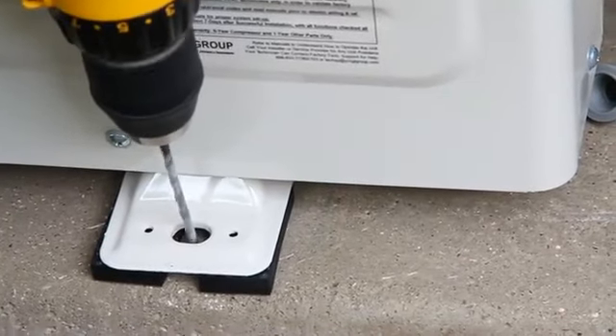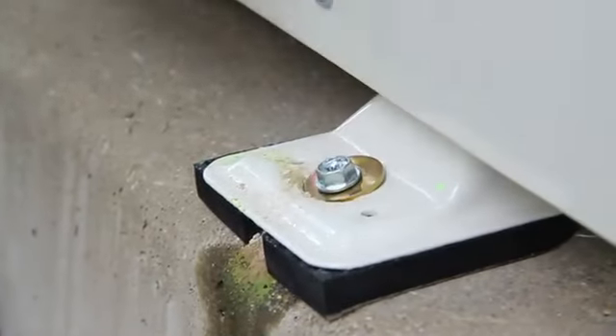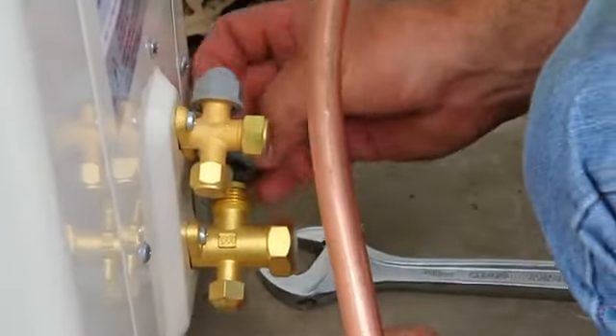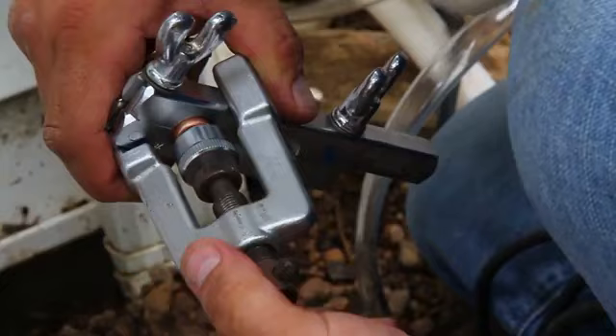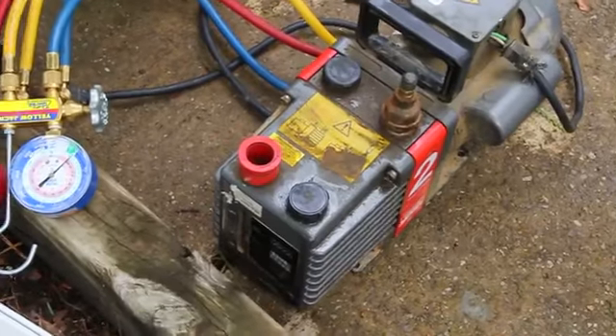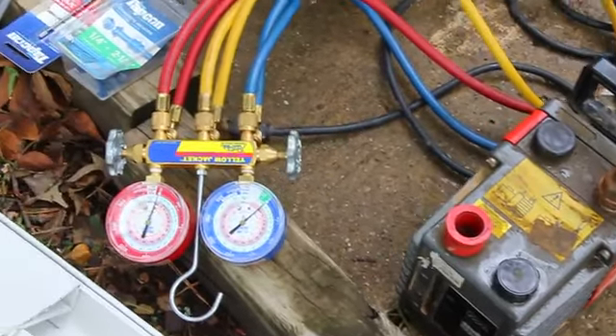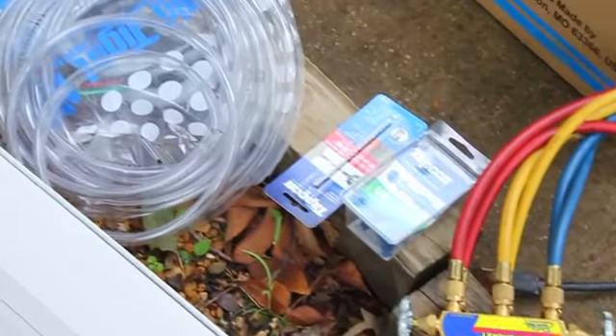When the outdoor unit is properly placed on the pad and anchored, you may remove the flare nuts from the service valves. If you are using prefabricated line sets, then the flare nuts may be discarded. But if not, they may be flared onto the lines that will be connected to the system. Before you start doing any cutting, you need to make sure all the pieces are ready, and you need to consider the proper tubing configuration.